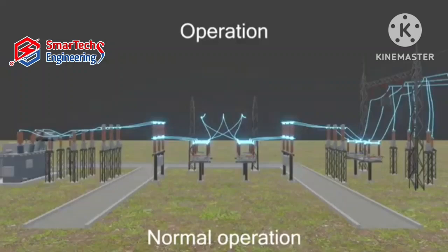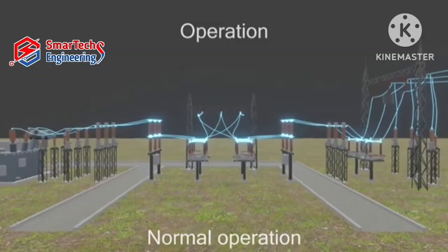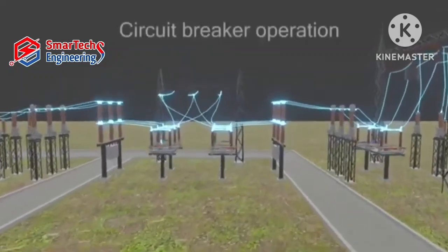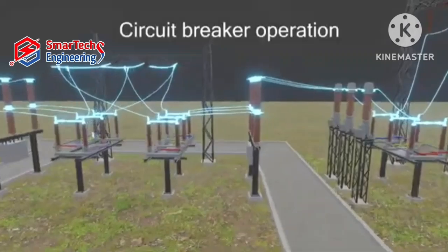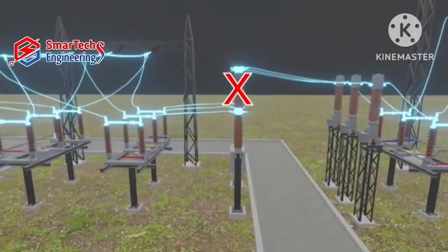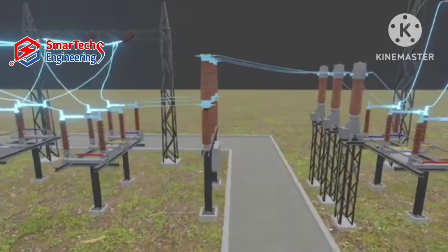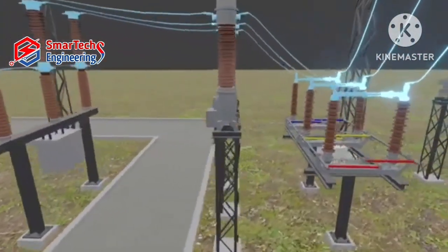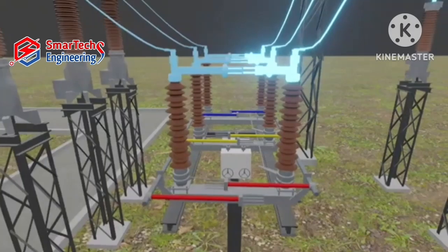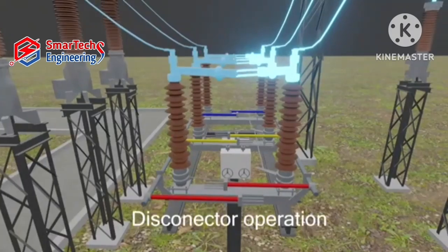Now you can see the normal operation. If we need to disconnect the line, first of all we will open the circuit breaker. Now you can see we are opening the circuit breaker. After opening the circuit breaker, we open the disconnector switch. You can see here we open the disconnector switch.